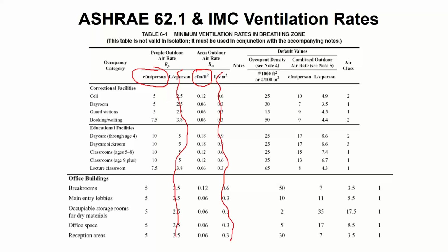The reason we did that is because we want to make you do math. No, I'm just kidding. The reason we did that is for the purpose of demand control ventilation, which I'll explain in about 15-20 minutes. But we had to split it up. So what it means is a given space is not always the same density of occupants. I may have 8 by 8 cubicles with 100 people in there, or I may have 20 foot by 20 foot private offices with 13 people in there for the same square footage. So it's not always the same.